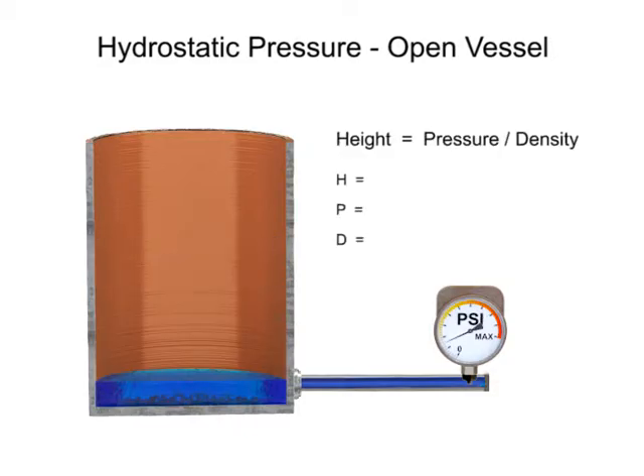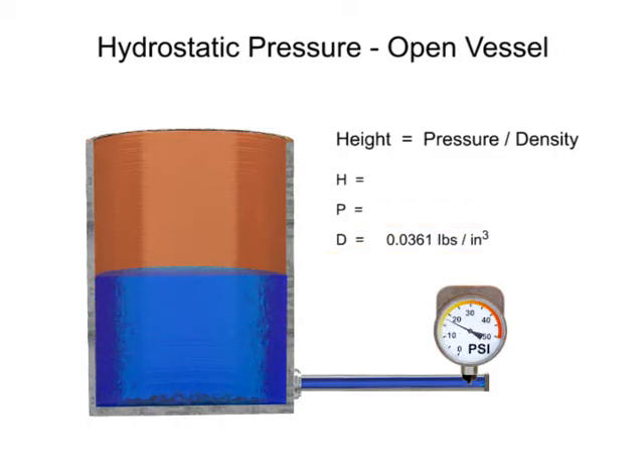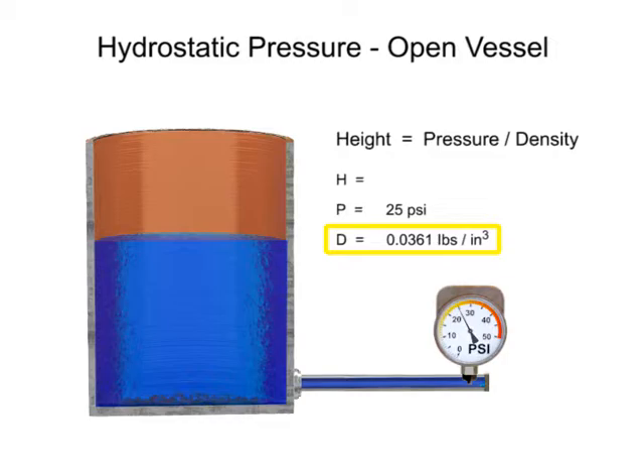To find pressure, a gauge is placed at the bottom of the vessel. With water having a density of 0.0361 pounds per cubic inch, the level of the fluid is calculated by dividing the head pressure by the density of the fluid.